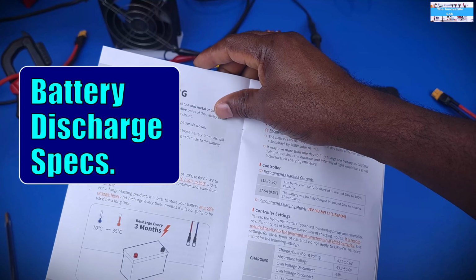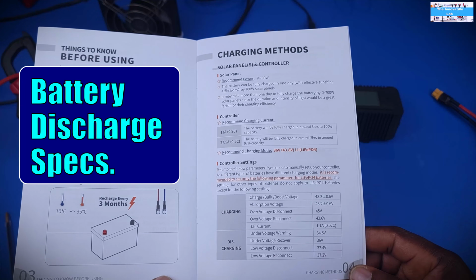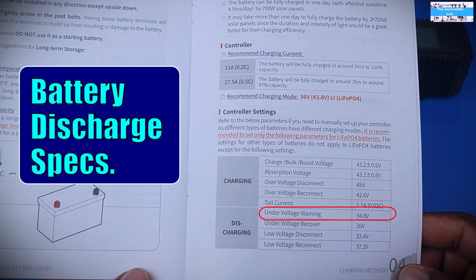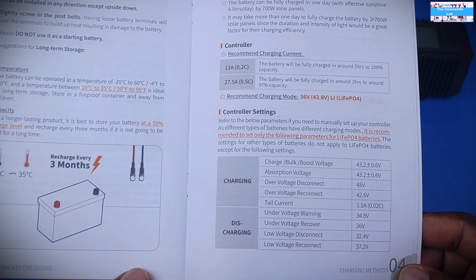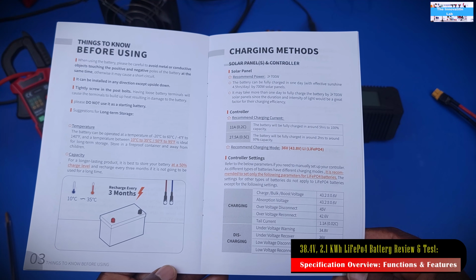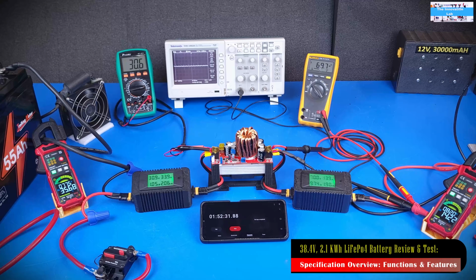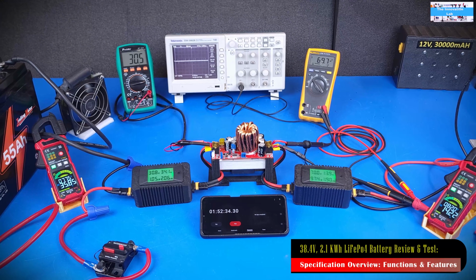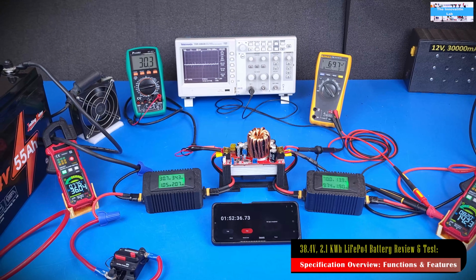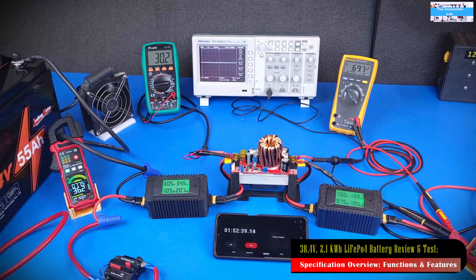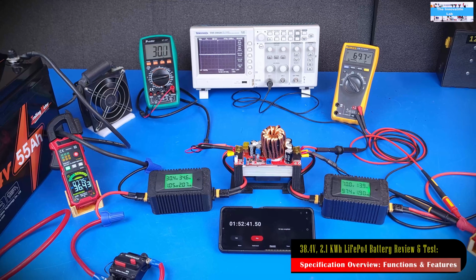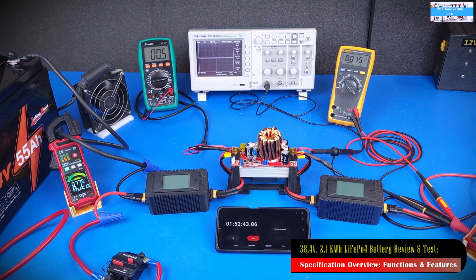Now looking at what happens during the discharge phase, the battery has an undervoltage warning of 34.8 volts, undervoltage recovery of 36 volts, low voltage disconnect of 32.4 volts, and low voltage reconnect of 37.2 volts. The low voltage disconnect is the most important one, the trip point of the battery. As you're discharging the battery with load applied, once you get to about 32.4 volts, the BMS should trip at that point, protecting the lithium phosphate battery cells inside.